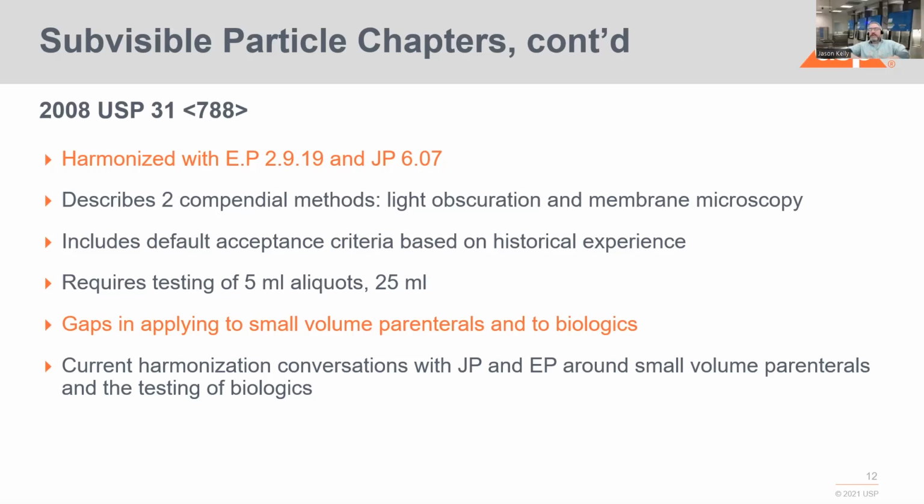Absolutely, Desmond. And also as the technology in the light obscuration field, where we develop liquid particle counters, is going down to smaller and smaller sizes, a lot of that has been driven from a different industry, the semiconductor industry, where the line widths on their chips now get down to around 5 nanometers. So to get higher resolution, obviously we need to move away from light obscuration to a light scattering technique in the liquid space. But as we move further and get more resolution, I think that will have an impact on your standards as well.